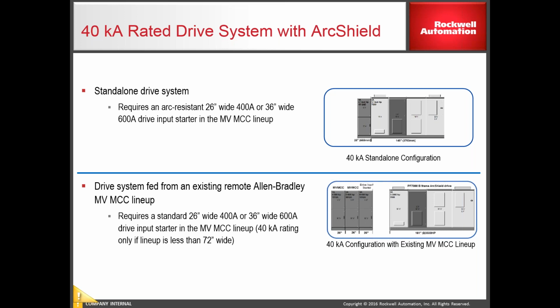And then with the 40 kA rating, with the inputs, you don't need an input line unit, but you need an input starter. And it's got to be at least 26 inches wide for 400 amp or 36 inches wide for 600 amp in the standalone configuration. And then again with the MCC lineup, 26 inches wide for 400 amps and 36 inches wide for 600 amps in that MCC. So you just cable over to the drive and you still achieve the ArcShield rating.